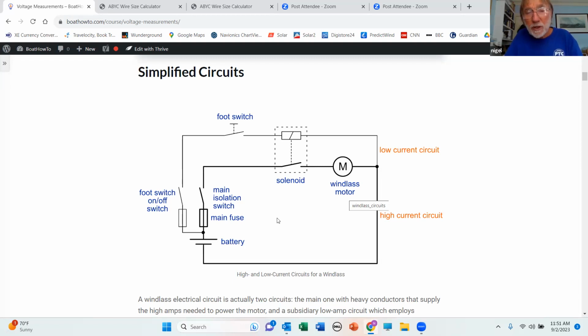So in theory, if we have a perfect circuit, if we test across the battery posts to see what the voltage is, the battery voltage, basically we've moved the battery to the load. We should also measure battery voltage across the load. In fact, we're going to read a little below battery voltage because of the voltage drop in the circuit. But it's going to be close, within 10%, as long as the circuit has been properly established. So again, if we think about, we've got all the switches closed. What we've done on this side of the circuit, we've effectively moved the battery post up to here, the positive post. On this side of the circuit, we've moved the negative post to here. And that's a function of the wiring. It's basically to move the battery posts up to the load.